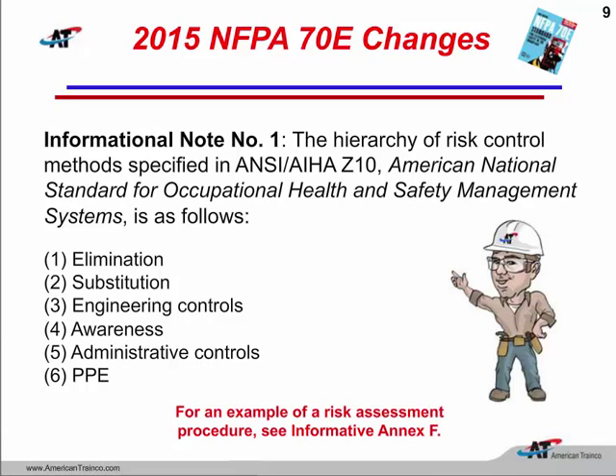Maybe we have an operator whose tasks include resetting an overload. He has to open up the control panel and put his hand inside, where there are definitely some exposed energized conductors and parts, and press a reset to get his machine back up and running again. Well, if we want to eliminate that risk, we'll locate that reset function on the outside of the panel so that he does not have to open it up, and he will not be exposed to any type of hazard then. There'll be no shock hazard, no arc flash, no arc blast, because there will be no energized exposed conductors or parts.